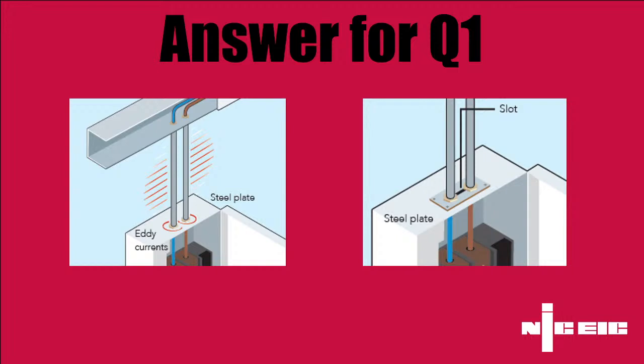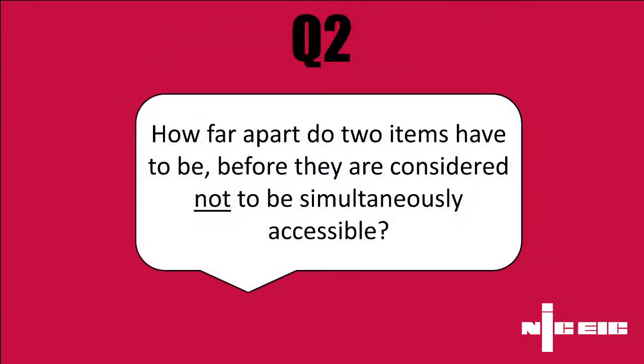Another one that's held over is, again, another classic to the helpline. How far apart do two items have to be before they're considered not simultaneously accessible? Because we've got a lot of situations where we're not allowed to have two items that could be of a different potential, a different earthing system, simultaneously accessible. So what are our guidelines on distances required to prevent simultaneous accessibility?